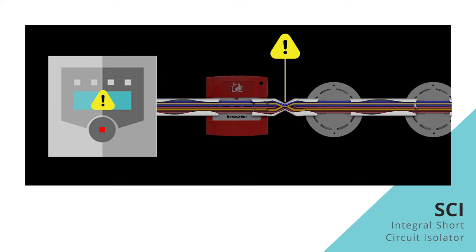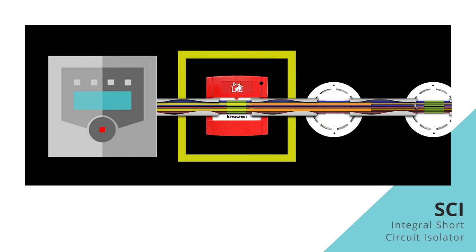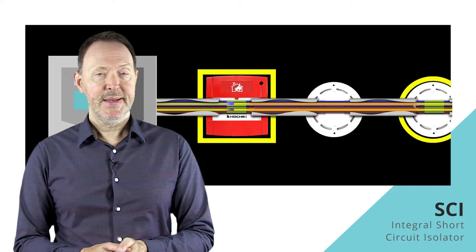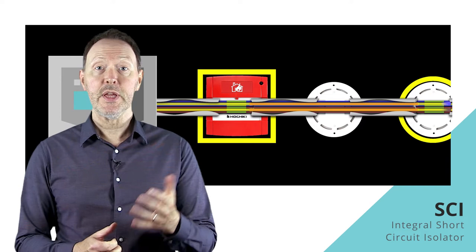Without voltage on the loop, the fire control panel can't receive any data from any device, and so in effect the whole loop of devices is lost. In this second example, this manual call point and this smoke sensor both feature an integral SCI. Short circuit isolators are essentially electronic components within a device that will monitor the incoming and outgoing voltage passing through the device from the loop cables.